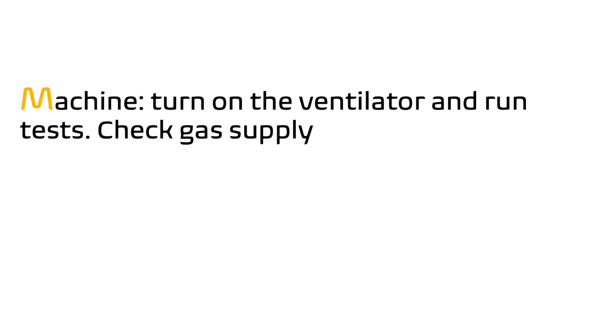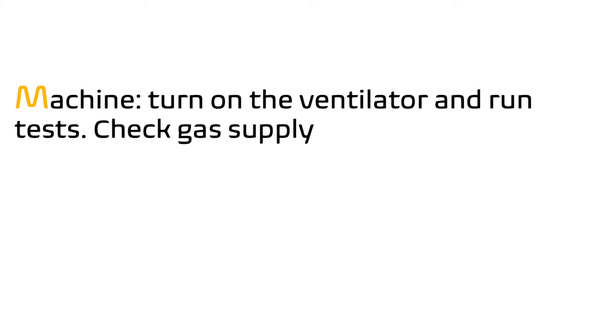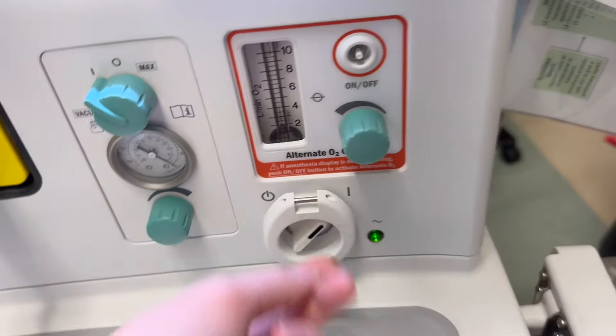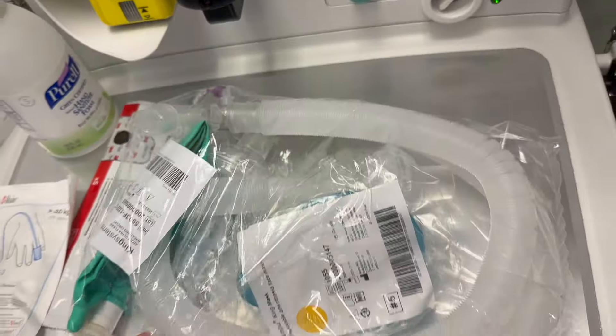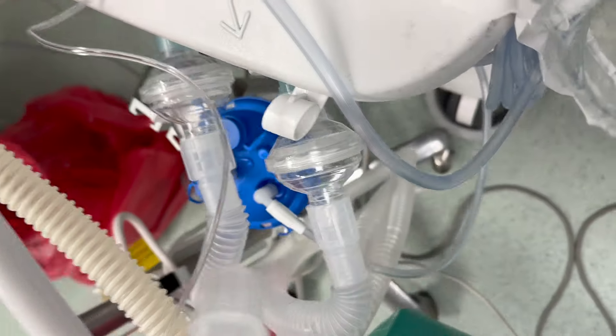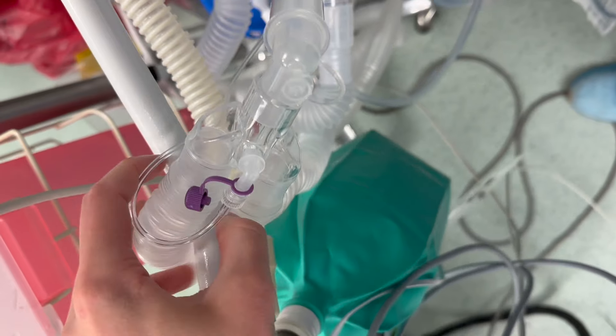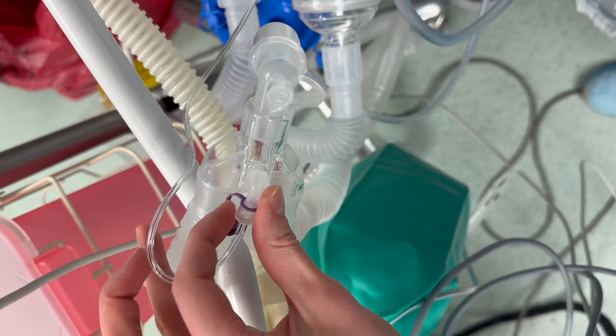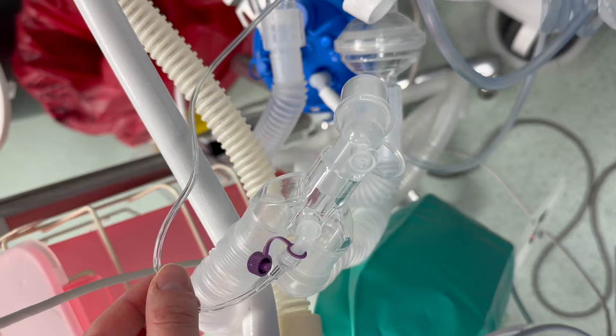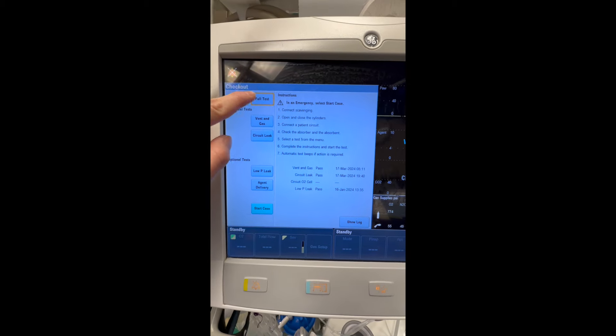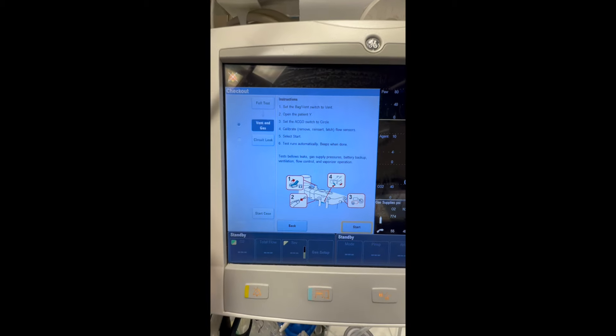It also means checking the gas supply of your oxygen tank as well as your anesthetic gases. The first thing to do is to turn on the ventilator and assemble your circuit. Remember to remove and reattach your flow sensors prior to connecting your circuit to them. Attach your end-tidal CO2 monitor to the purple port instead of the elbow connector, in case the elbow connector needs to be removed. Remember to attach the other end of the monitor to the ventilator machine.